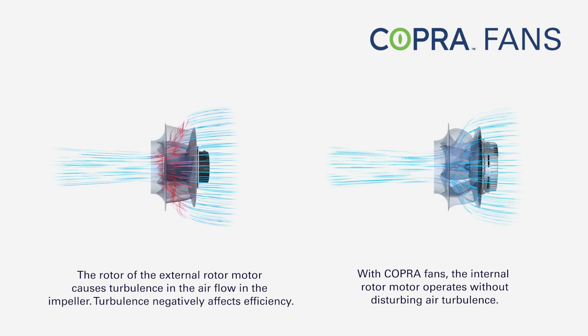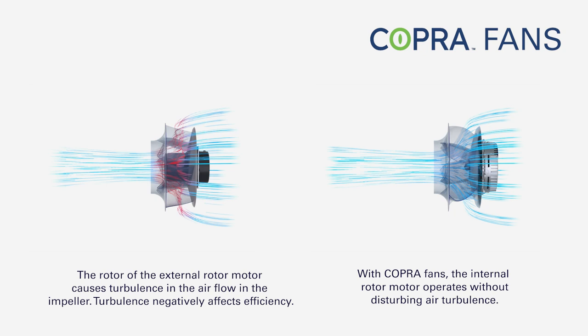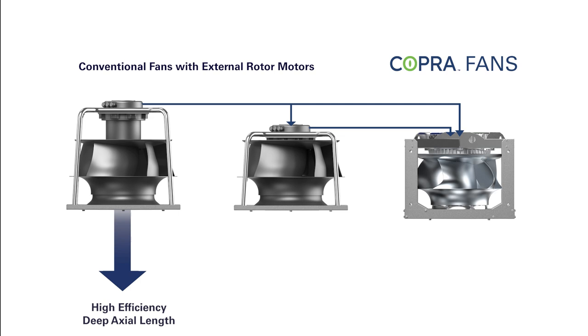With COPRA fans, it is now possible for a system with an internal rotor motor to operate without disturbing air turbulence. Pulling the external rotor motor out of the impeller provides high efficiency when compared to a motor located in the impeller, but makes the system longer.